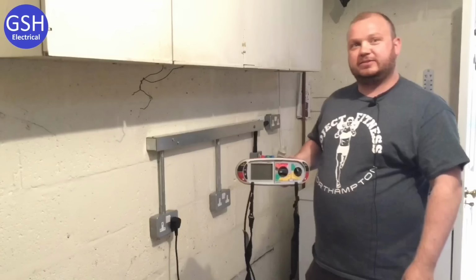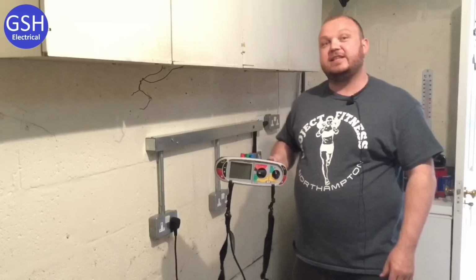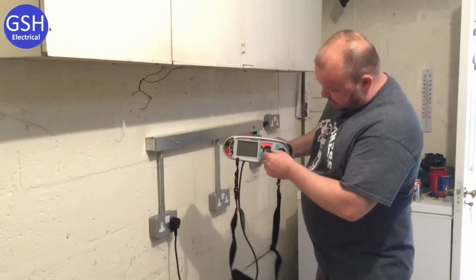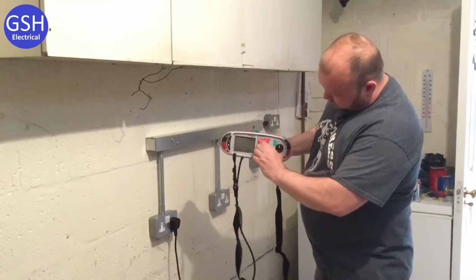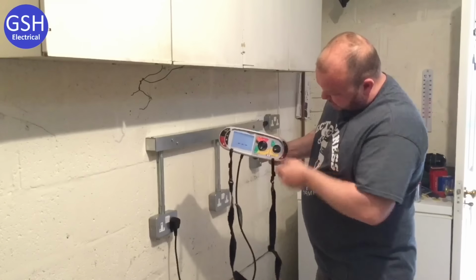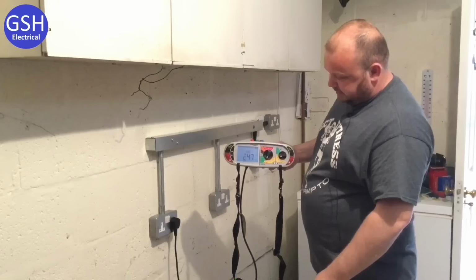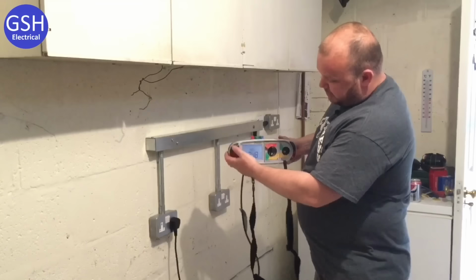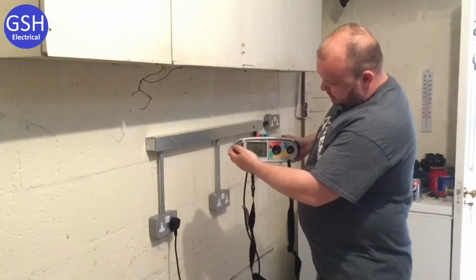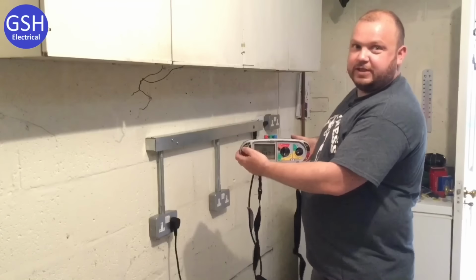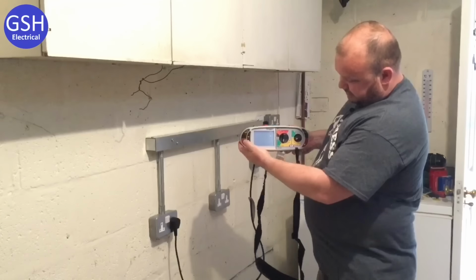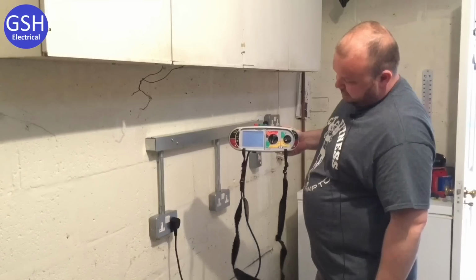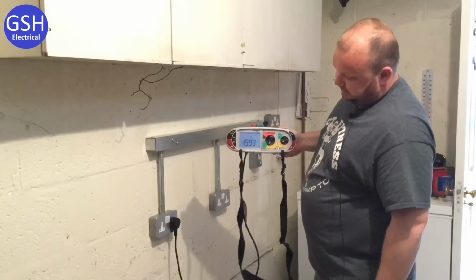So Mark, what are you going to do now for me? I'm going to do the RCD test. Good, can you set your test instrument up for us? Yeah, we're going to switch it on to half times. Okay. And then 30 milliamps. Okay, brilliant. What angle are we in? We're going to go 0 degrees. What do you expect to happen when you do this test? I expect nothing to happen on this test. Okay, let's see that then. Yeah. Okay, brilliant. Good reading.